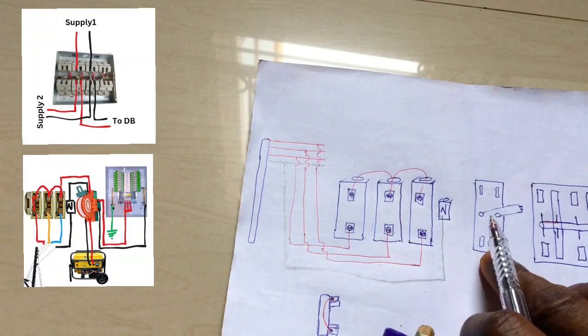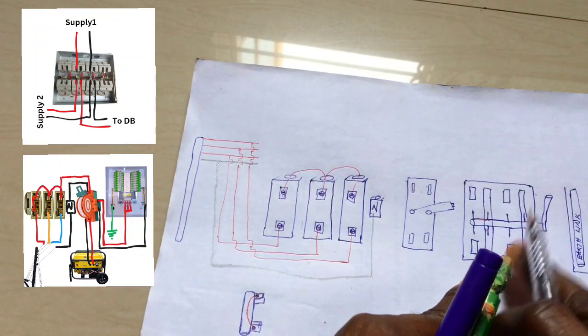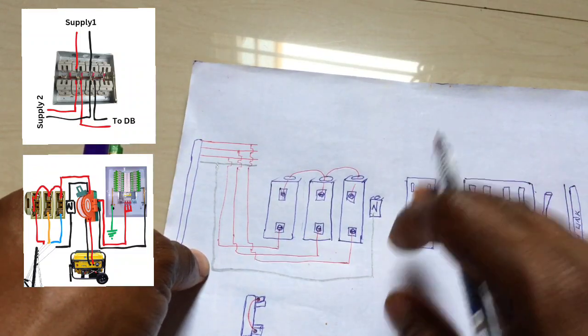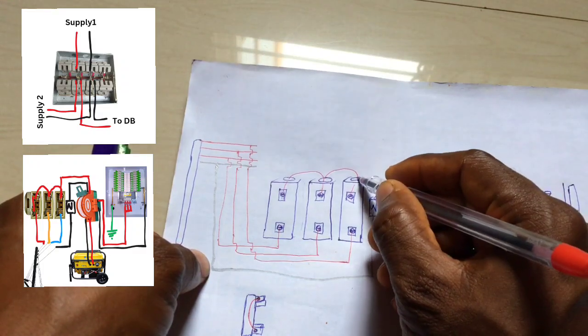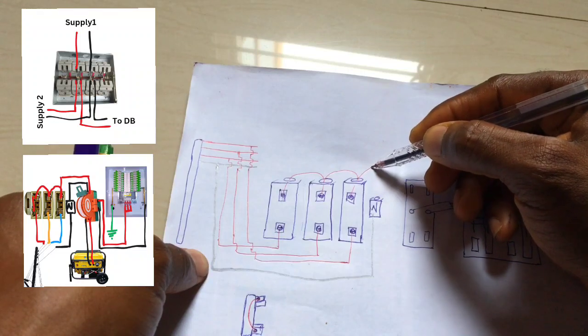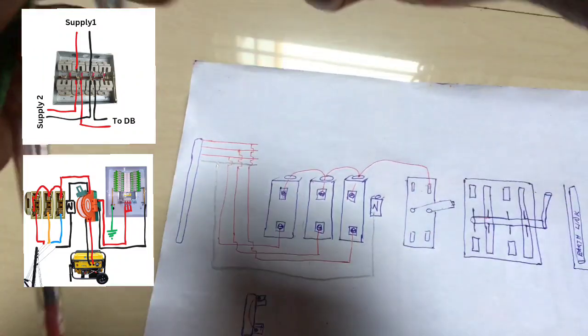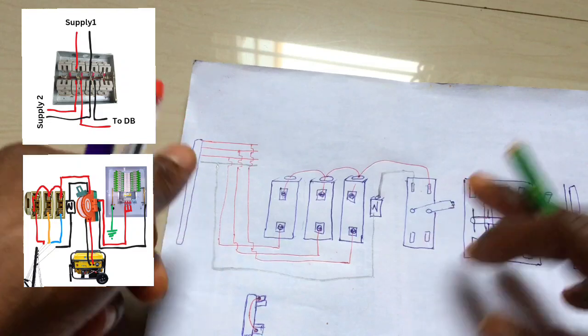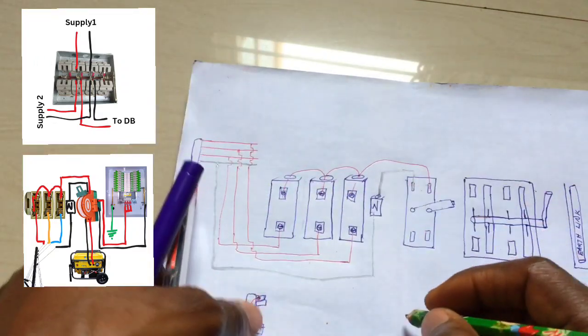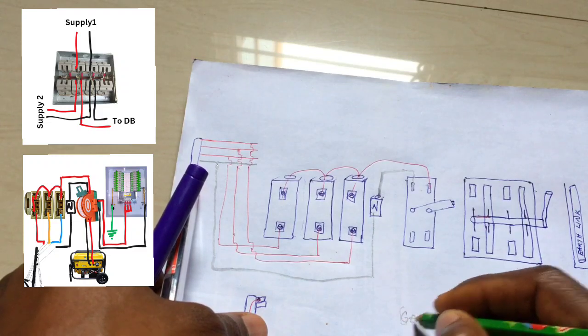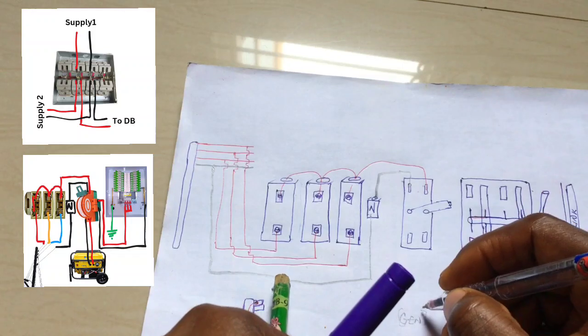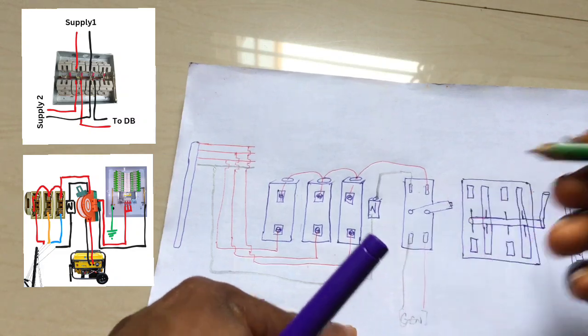Now we continue. You can either use a knife switch changeover or a gear changeover. Let's connect the knife switch changeover — from here, live comes here and neutral comes here. The essence of a changeover is when we have multiple sources of power. If we have a generator, its live and neutral will come to the second inputs. This can also be a solar inverter output.